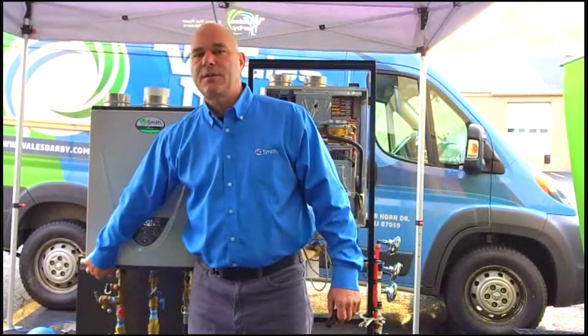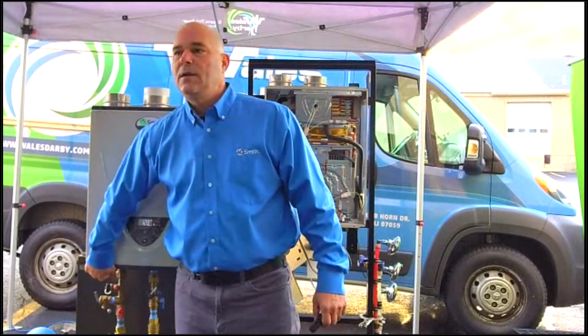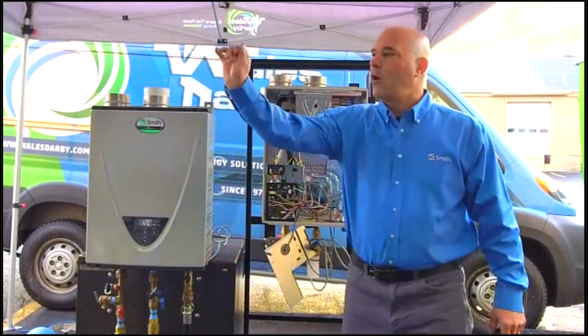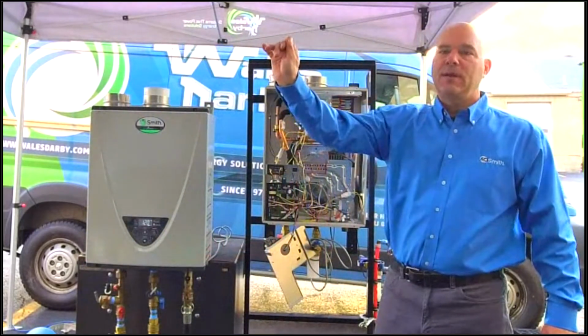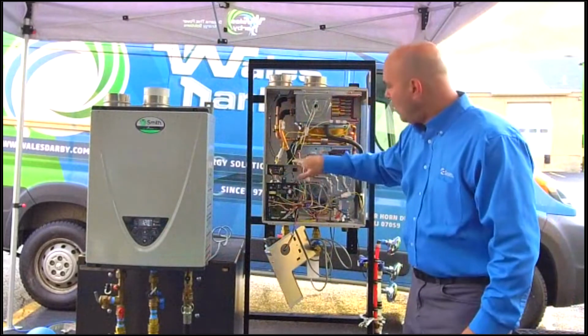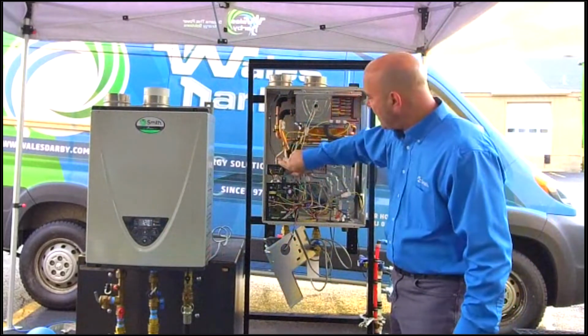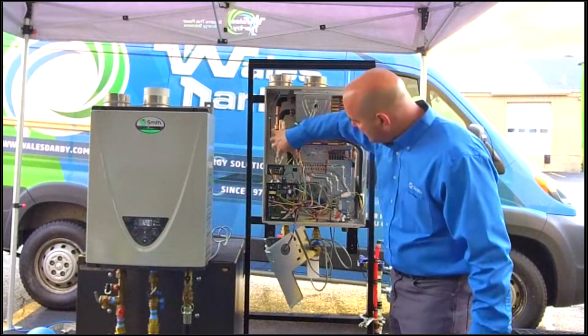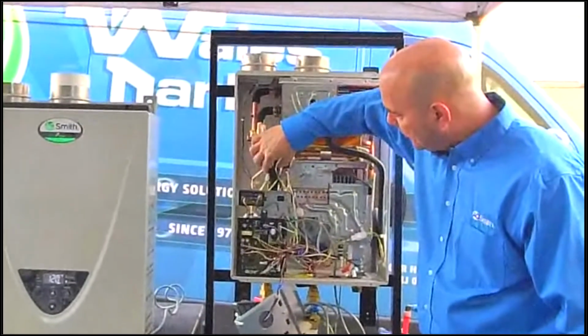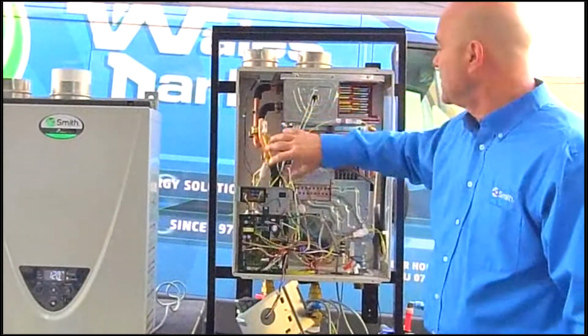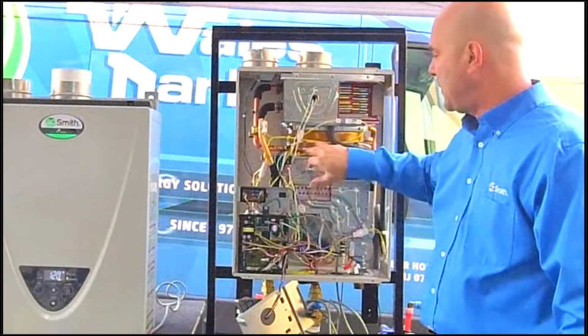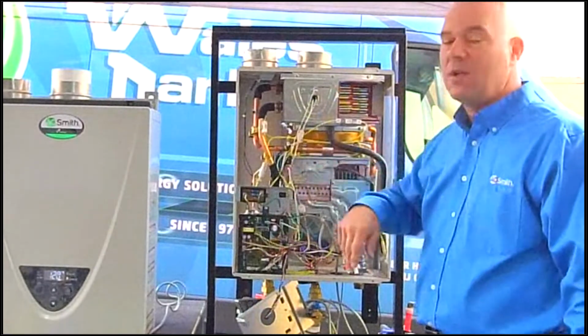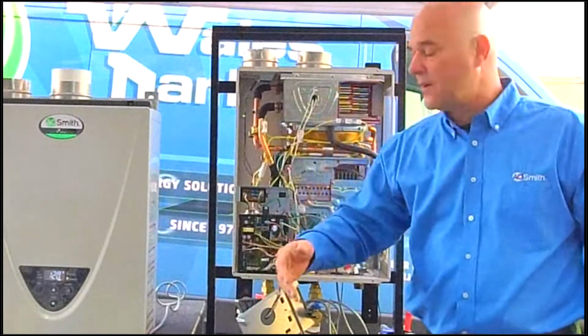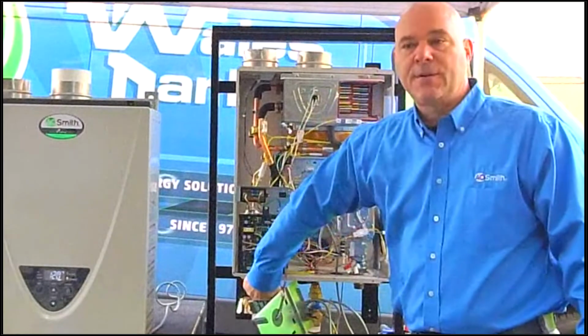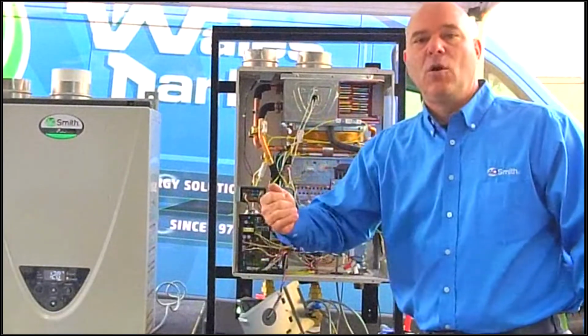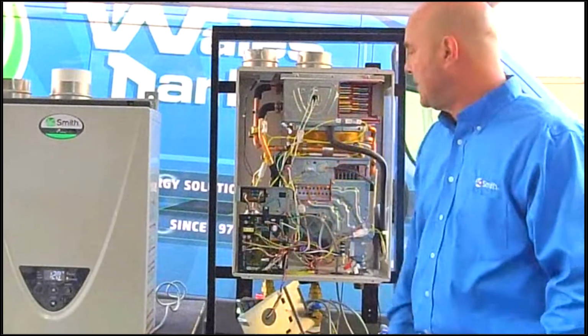And the first time you go to turn this on, all the way over to the right, there's a little black bleeder there. You're going to open up that black bleeder port, and that is going to make sure all the air gets out. This little copper line right here is attached to the bleeder port. What that's going to do is make sure we have all the air out of the piping, all the air out of the primary heat exchanger before you fire it, so you don't dry fire. You have the opportunity right under here to take the little plastic port, open it up, and then close it when you're done.